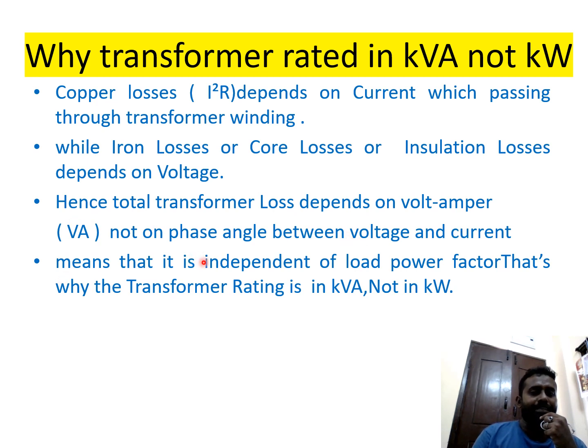Hence total transformer loss depends on volt ampere, not on the phase angle between voltage and current. Means that it is independent of the load power factor. That's why the transformer is rated in kVA, not in kilowatts. This is the exact reason for why a transformer is rated in kVA. Also we don't know which load you are going to connect to the transformer, so it should work for all the different power factor loads which are to be connected to the transformer.